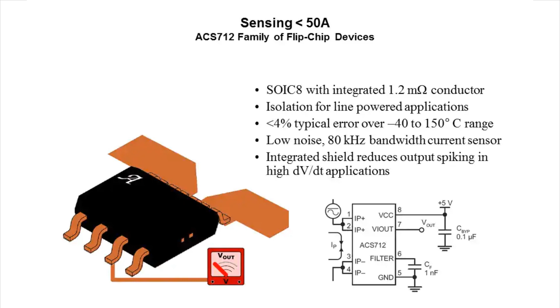It does have to be in series with the circuit, but you can see it's on one half of the chip, and it can be high side, low side, or middle - anywhere you want, because it's completely isolated electrically. The output is a voltage, either centered at 0 and going above and below, or ratiometric, or from 0 upward if it's only positive voltages. Either way, this is the old generation.